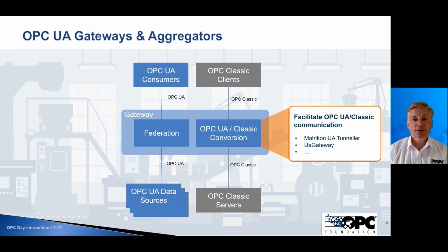So in this case, if you have an OPC-UA gateway, one of the things that you want is a component that would enable an OPC Classic client to talk to it, and therefore you need a translation in order to translate from the Classic client to the UA server that the OPC-UA gateway is. Or you need the OPC-UA gateway to be able to communicate with an OPC Classic server. So even though it's UA based, it then translates and actually talks OPC Classic to the server, but it maintains its own OPC UA functionality, let's say, internally.